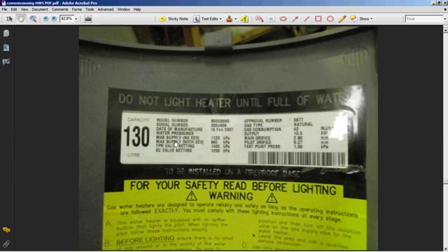On the back of the panel that comes on the hot water service with the instructions, it gives you the test point pressure there. So it's meant to be 1 kPa.